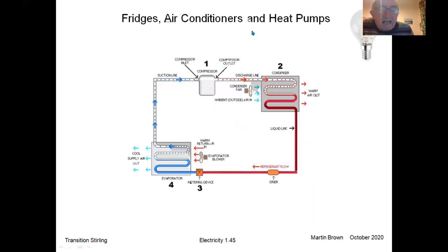Fridges, air conditioners, and heat pumps, they're all the same thing. They all work on the same principle. An air conditioner is a heat pump that's running the other way around, you might say, because with an air conditioner you want the cold bit of it, and with the heat pump, you want the hot bit of it. Fridges are the same, they all work the same way. We have a compressor, we compress a gas, that gives it energy, which makes it hot. So this bit of the system is hot, and that's where we get our heat from if we want it. So if we're heating, like with a heat pump, this bit is hot.